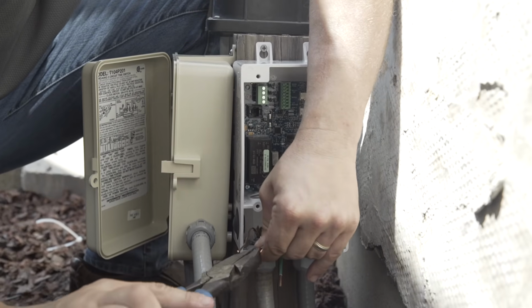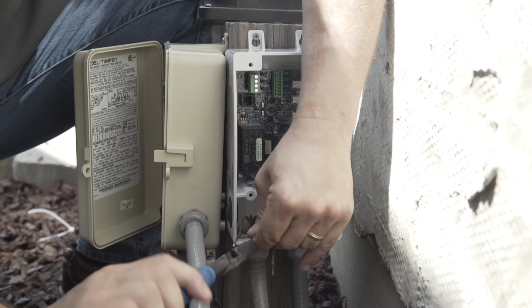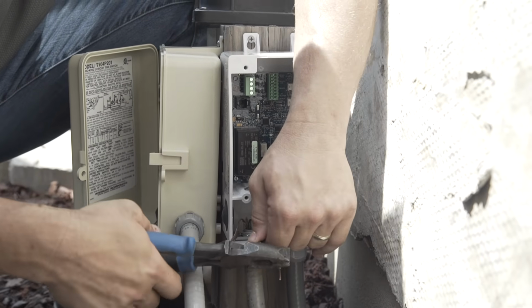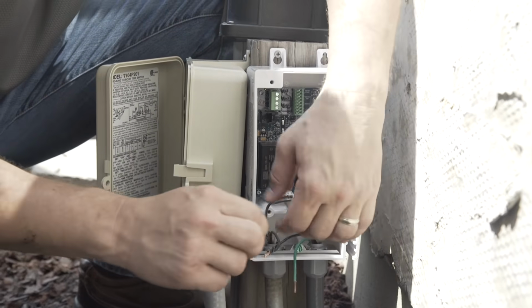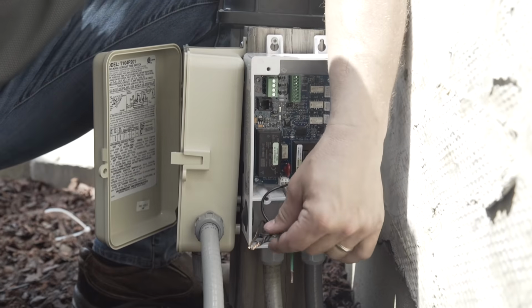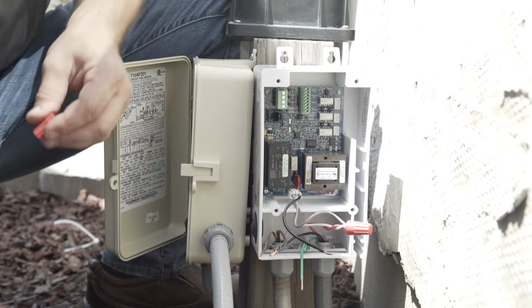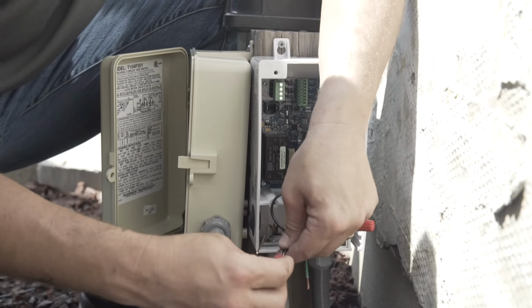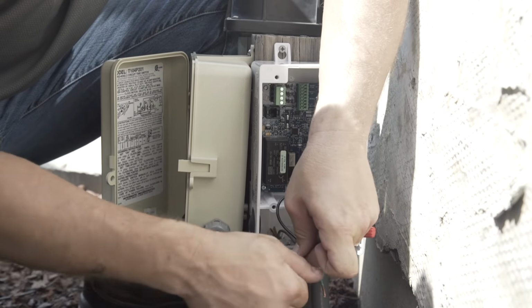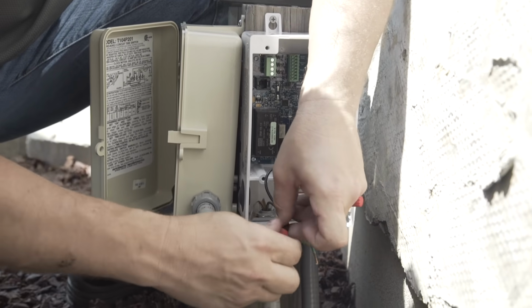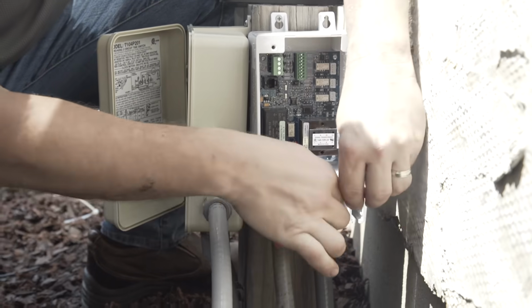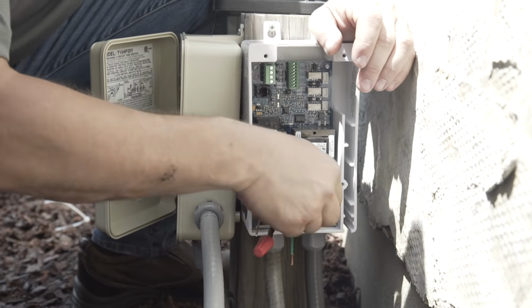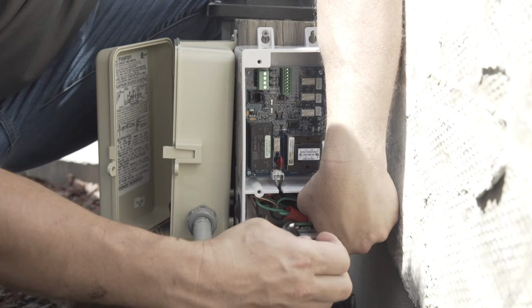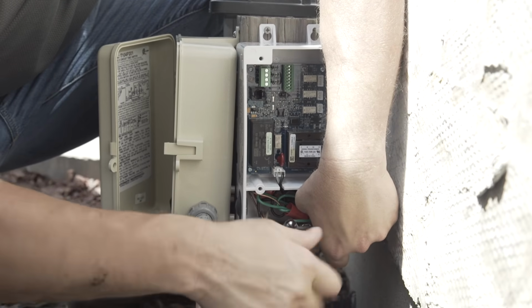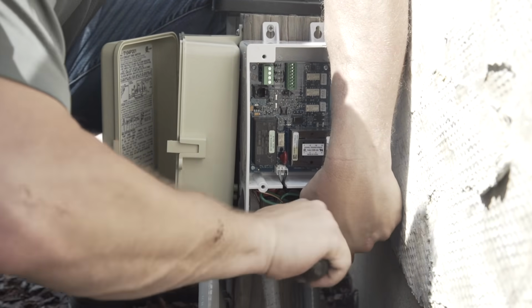When wiring the VS Omni through the hub input power must match the pump's power requirements. In this case, we have 230 incoming volts. Connect the wires that come from the load side of the time clock to the hub connection wires. Next, add the pump wires to these connections, capping the connections off with the included wire nuts. It is important to also connect all ground wires properly to the grounding lug.